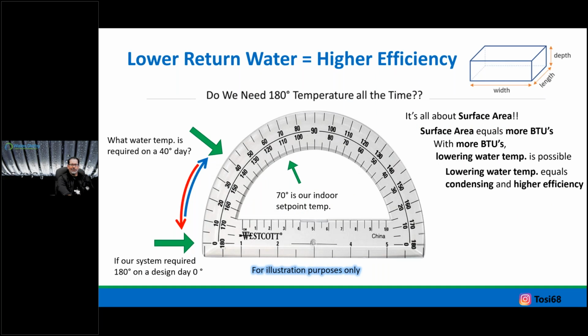This is an old slide. I just really had some fun building this, and the mindset was back really before even lowering water temperature, selling outdoor reset for cast iron boilers. Partial reset, right? So cast iron is typically a non-condensing boiler, and there's a threshold. I don't want to go below 140. It's cast iron. If I'm condensing, I'm almost deteriorating that cast iron, as strong as we think it is, but over a short period of time or a lifespan less than what we typically see for cast iron, we could be corroding because we're condensing in a non-condensing piece of equipment.